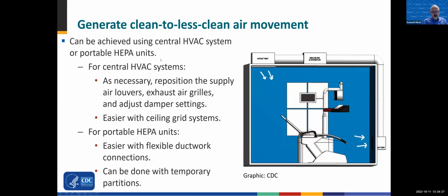Generating clean to less clean air movement. This is one of the areas we've had a little bit more questions on. What we're really talking about here is being strategic. Where is the air going to leave the room? Where is it going to enter the room? In the graphic on the right, we have a dental chair. The dental patient is the source of potential infectious aerosols. We're using a recirculating HEPA system to establish an airflow within that space. The contaminated air goes in at the foot, it comes up, it gets cleaned, and it comes out at the top behind the patient, and you create this circular pattern that quickly controls what happens to those infectious aerosols after they're generated, and prevents them from going around the entire room.